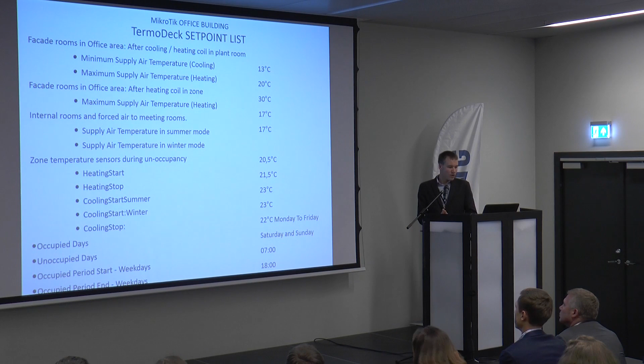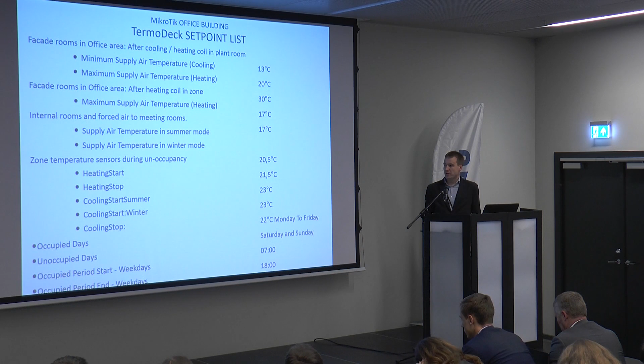So there are some numbers of air temperatures and basic thermodeck starting point temperatures, but everything is controlled by BMS, so the temperatures can be adjusted as needed, and this system could also be modified later depending on the needs and actual usage of the building, because it's now designed for a typical working day period, but in real life this working day could be a bit different. So through the BMS, this algorithm of air temperatures can be adjusted.